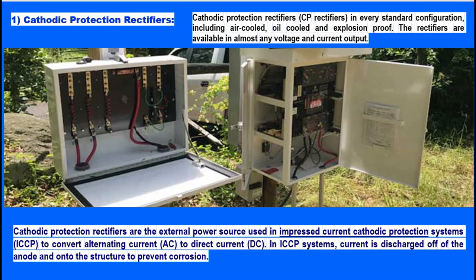Cathodic Protection Rectifiers are the external power source used in Impressed Current Cathodic Protection Systems (ICCP) to convert alternating current (AC) to direct current (DC). In ICCP systems, current is discharged off the anode and onto the structure to prevent corrosion. CP Rectifiers are available in every standard configuration including air cooled, oil cooled, and explosion proof, in almost any voltage and current output.